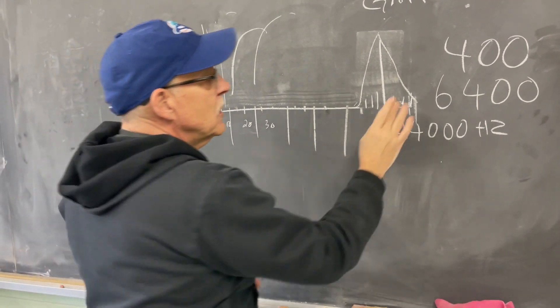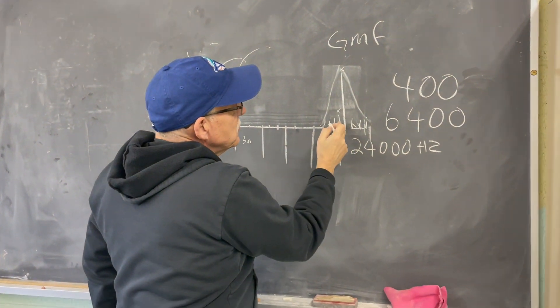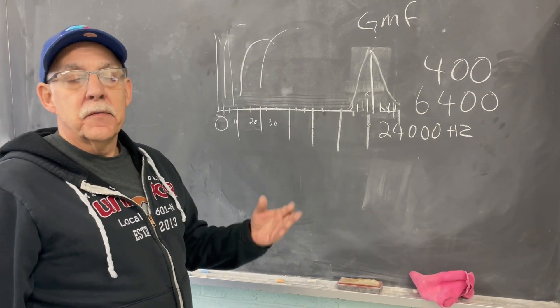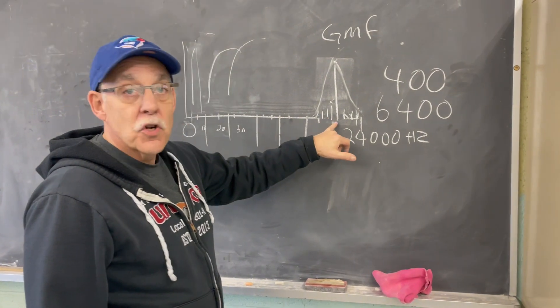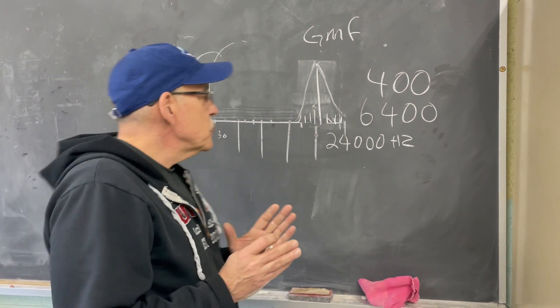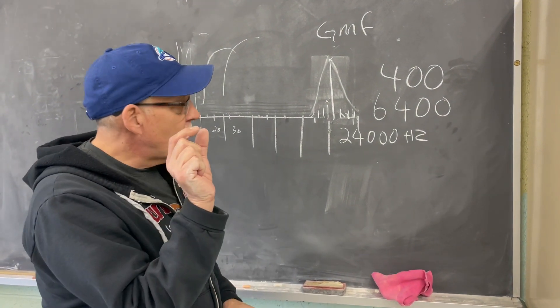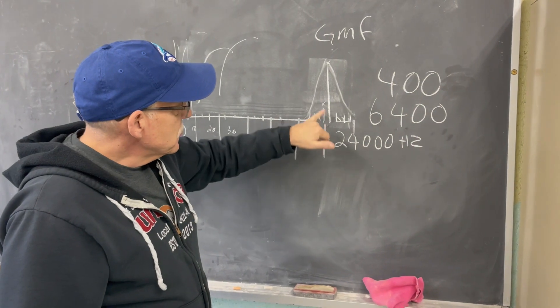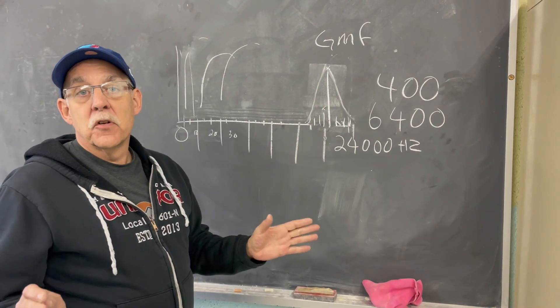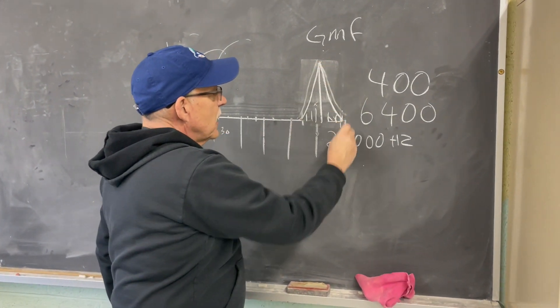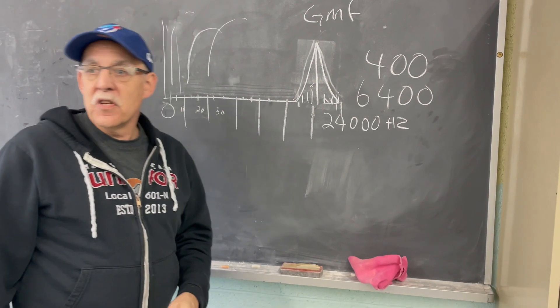The sidebands around the gear mesh tell us about the bad gear. We measure from the primary frequency over to a sideband, and generally that sideband corresponds with the turning speed of the bad gear — an eccentric gear comes up at turning speed, a bad tooth shows up in the sidebands. The more sidebands around the primary, the more severe the problem. At 400 lines you just see one wide peak and can't do this analysis. So that's the setup: F-max sets the spectrum span, and lines of resolution sets the picture clarity.